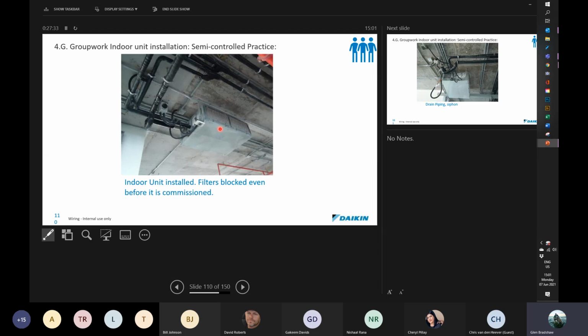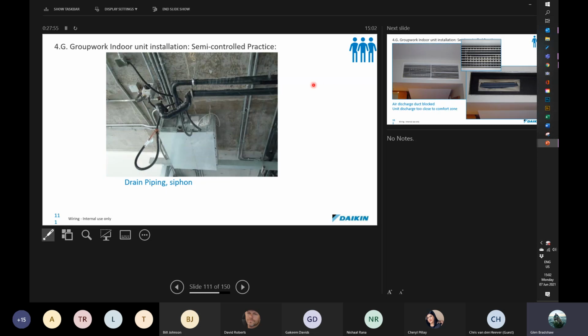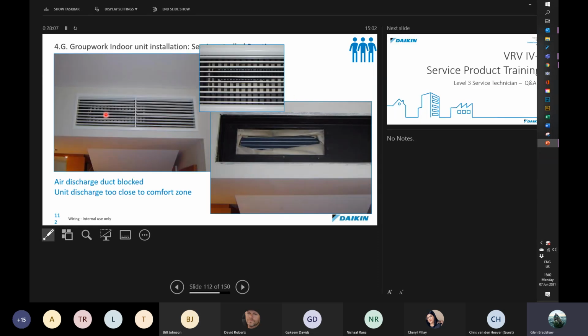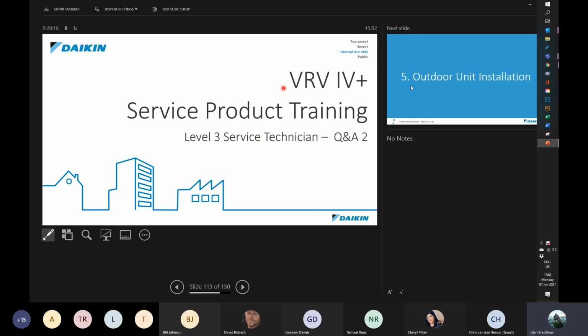once you install units, to reduce the ability for other people on the site to start turning units on. The unit should only be turned on by the commissioning engineers on the day of commissioning. Once other people start using them, they will start to abuse them. All right, here's piping. You can see this drain piping that's not installed too well. And over here we've got partly blocked off diffusers and things like that, which are not recommended. Right, so we're going to the end of the indoor units.